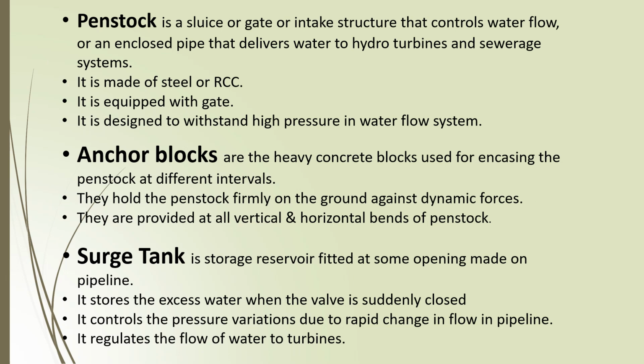Next one is anchor blocks. These are heavy concrete blocks used for encasing the penstock at different intervals. They hold the penstock firmly on the ground against dynamic forces. They are provided at all vertical and horizontal bends of penstock.